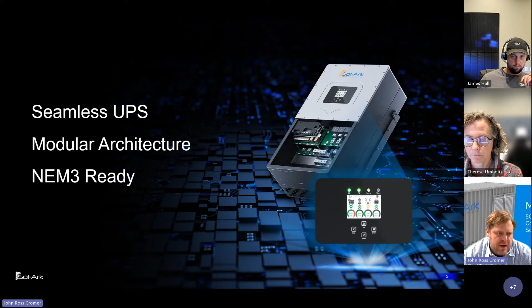So as that grid pass-through capability, GEN port, DC coupling capability, the grid connection that automatically isolates from the grid, and the controller that comes included with the Sol-ark, it has a time of day controller and a seasonal demand controller. And my favorite thing about the controller for this year is that when Net Metering 3.0 came out in California, we didn't have to change a thing about the controller for it to be net metering 3.0 ready. You don't even have to connect the internet to the inverter. You can program net metering 3.0 by just touching the LCD screen, going into the grid settings and saying sell back between 6 p.m. and 8 p.m. in August and September, for California net metering 3.0. So very easy to do California applications with this system.